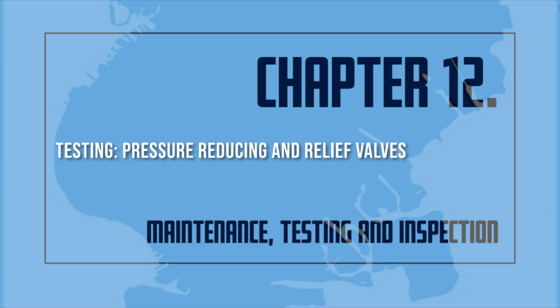25. Circulation relief. During the annual fire pump test, the closure of the circulation relief valve shall be verified to be in accordance with the manufacturer's specifications. Pressure relief valves. During the annual fire pump flow test, the pressure relief valve shall be verified to be correctly adjusted and set to relieve at the correct pressure and to close below that pressure setting.